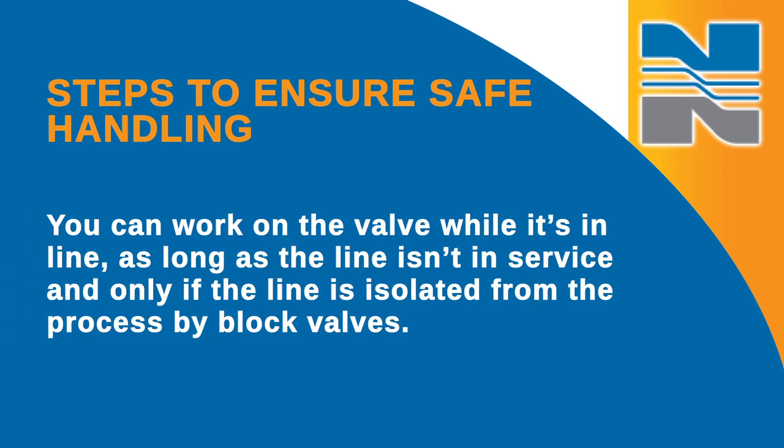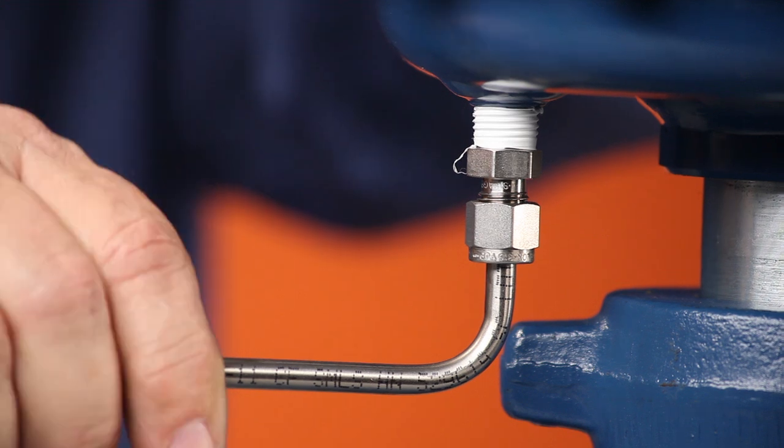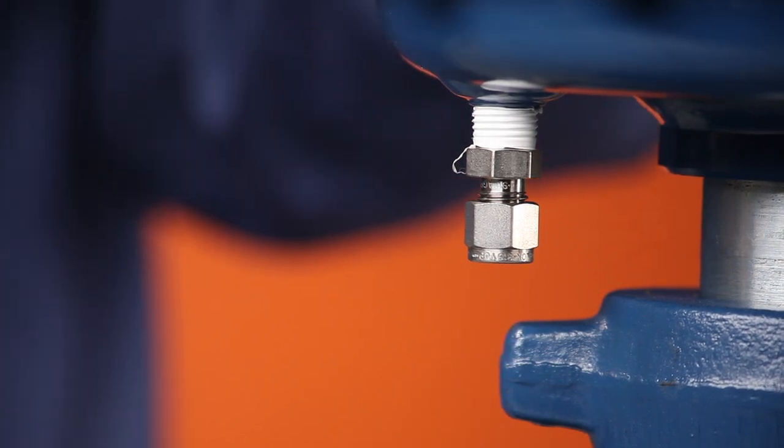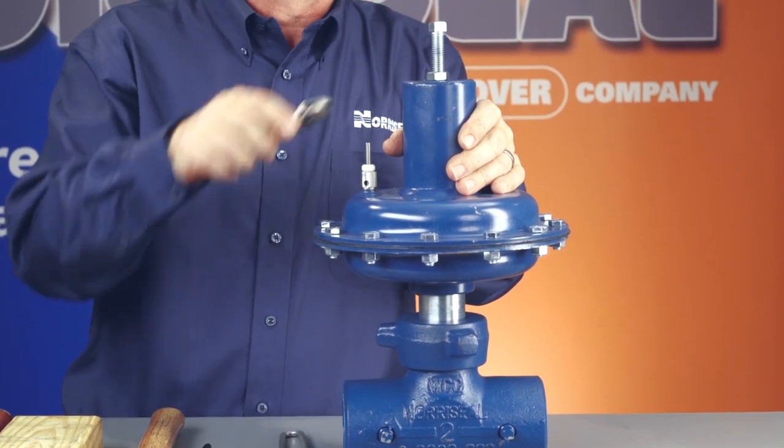You can work on the valve while it's in line, as long as the line isn't in service and only if the line is isolated from the process by block valves. To take the valve apart, you first want to vent and disconnect the supply pressure from the actuator. Then, you'll want to remove the spring compression.